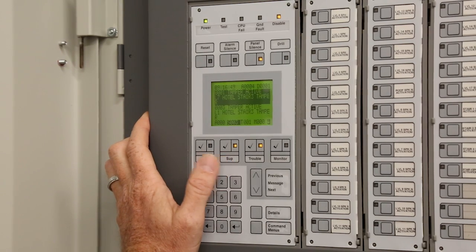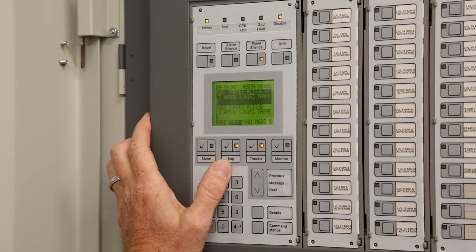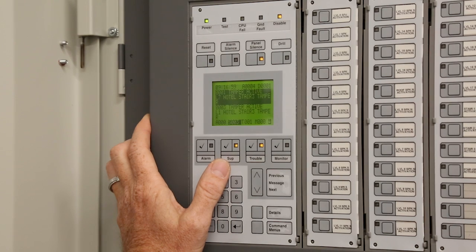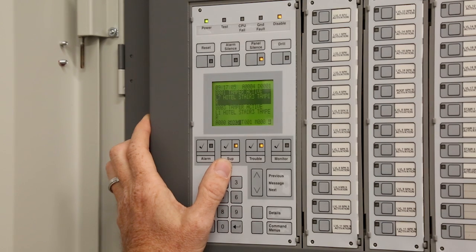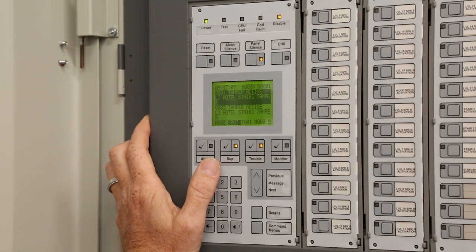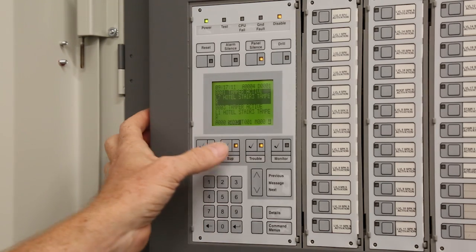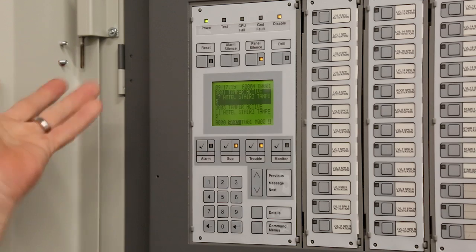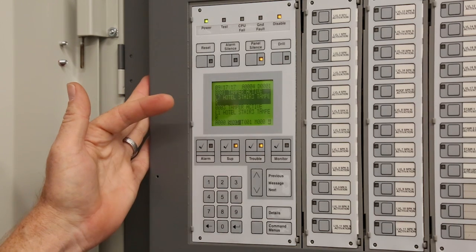Supervisories, on the other hand, do not notify the building. It just beeps at the panel. It shows you what it would be. Supervisory could be a tamper valve for your sprinkler system shut, could be power supervision for your elevators, or it could be your rooms. All your room detector smokes are independent. They are 120 volt, but they are monitored by here. So if the supervisory goes off in room 606, it will actually tell you right here.